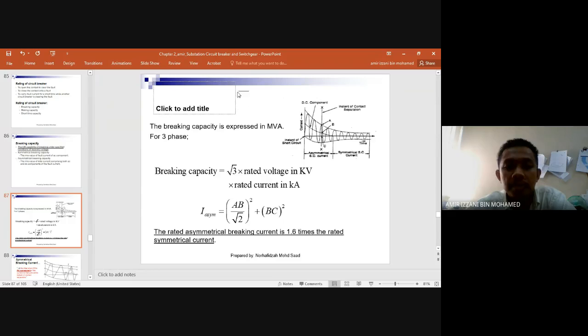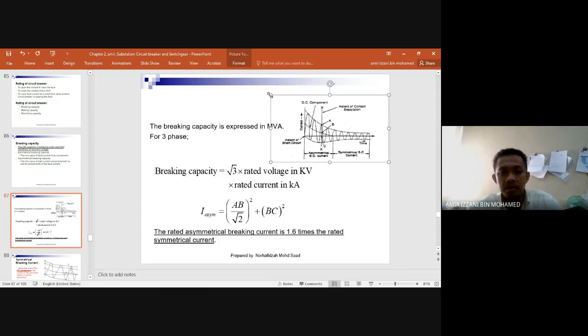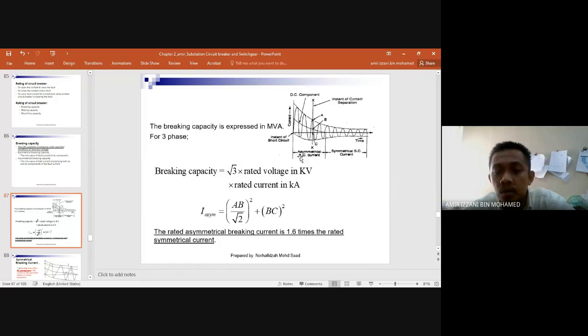The breaking capacity is expressed in MVA. As you can see here, this figure shows two components. The first one is asymmetrical. Here, you can see the voltage is shifted up, so it's not symmetry. And this one is symmetry. Symmetry means that the voltage of positive and negative cycles is the same. This one is not symmetrical. Like I said before, maybe this one is already 16 kilovolt due to the DC component, and the lower part becomes negative 6 kilovolt.